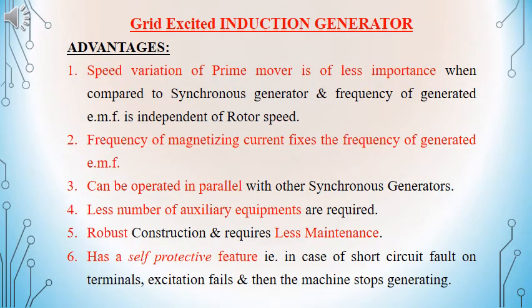We will now discuss the advantages of separately excited or grid excited induction generator. The variation in the prime mover speed will have less importance when compared with the speed variation in the case of synchronous generator. The frequency of generated EMF is independent of the rotor speed in induction generator; it depends only on the frequency of the magnetizing current, that is the frequency of the grid. Induction generators can be operated in parallel with other synchronous generators. It requires only fewer auxiliary equipments. It is robust in construction and requires less maintenance. It has a self-protective feature.